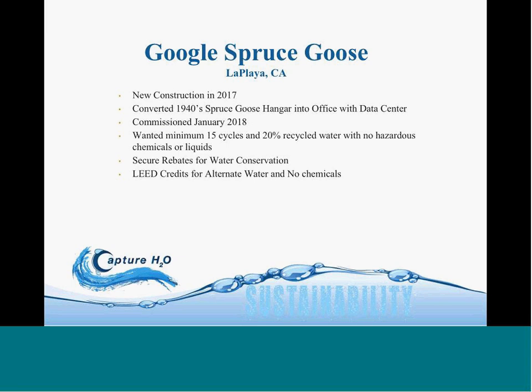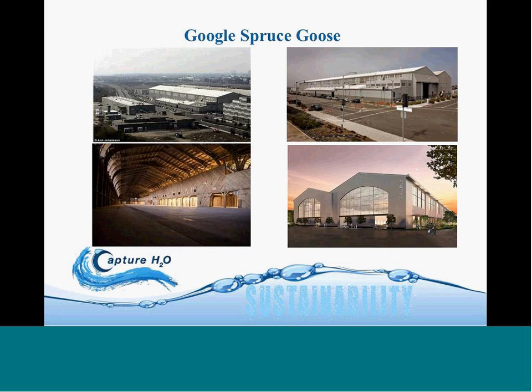When they designed the plant, they wanted a minimum of 15 cycles of concentration, meaning roughly about 7% blowdown is the most they wanted. And they wanted to be able to use at least 20% recycled water without having to use hazardous chemicals and liquid hazardous chemicals. This site secured some rebates from water conservation as well as LEED credits for using alternate water sources for the cooling system and reducing chemicals.